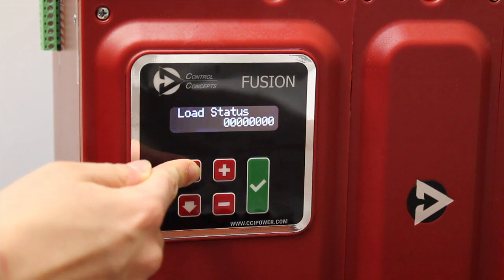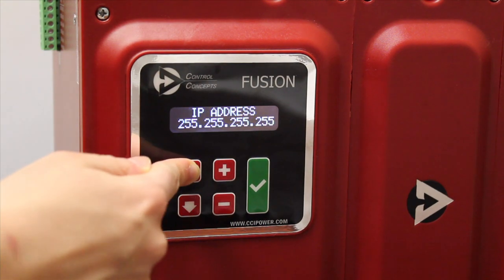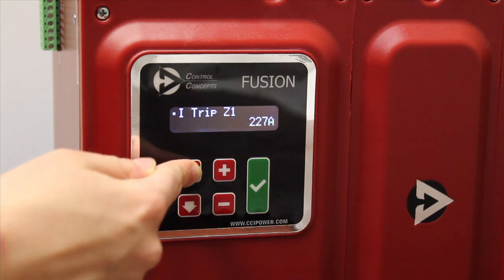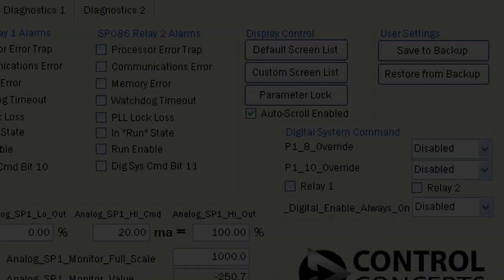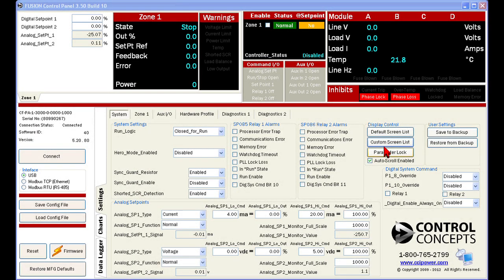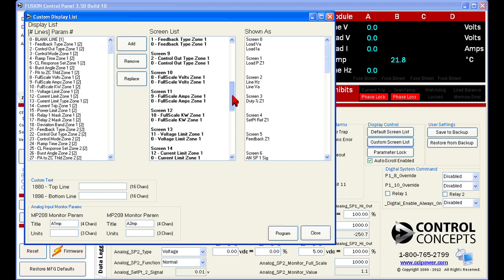The display control options dictate what information will be available on your controller's digital display. Clicking on default screen list returns the screen list to manufacturing defaults. Selecting custom screen list opens a new window. From here you can choose what relevant data appears on your controller display or create custom text. The controller can display a maximum of 50 screens. Each screen contains up to two lines of text. The screen list tells us which parameters are currently being displayed.